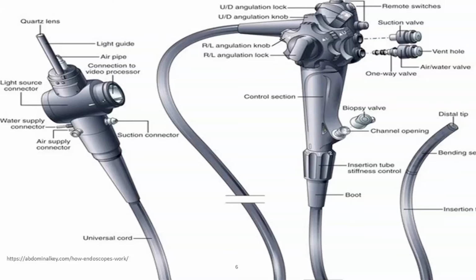These devices may have fiber optic or video capabilities, and this is defined by how the image is captured and transmitted. So fiber optic gathers an image via a series of lenses at the distal end of the endoscope. The image is transmitted to the eyepiece via fiber optic bundle. The video requires you to have a power source and a video system to view the image. So this is like your TV monitor type screen. The image is captured and transmitted as an electrical signal to the viewing monitor.